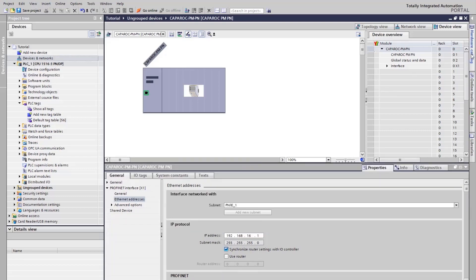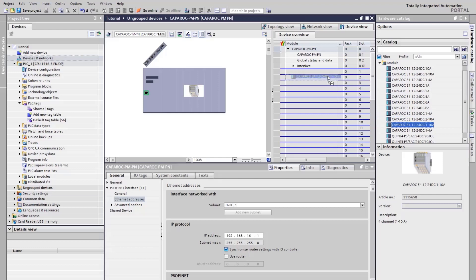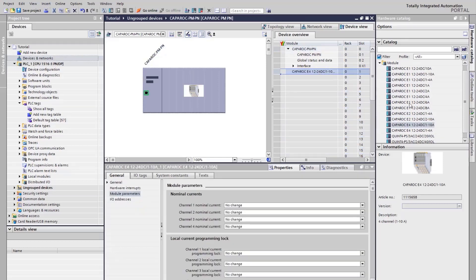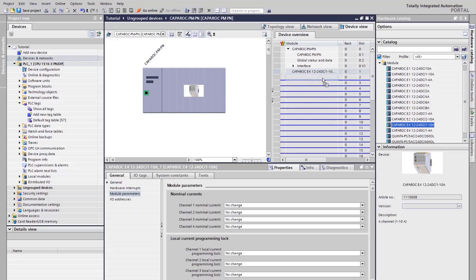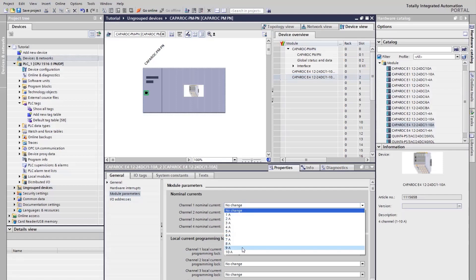Open the Hardware Catalog again and add further circuit breaker modules via drag and drop to your configuration. The maximum system size is 16 circuit breaker modules in combination with one power supply. If necessary, you can parameterize startup parameters for every module, beginning with a nominal current and locking functionalities up to the channel status.